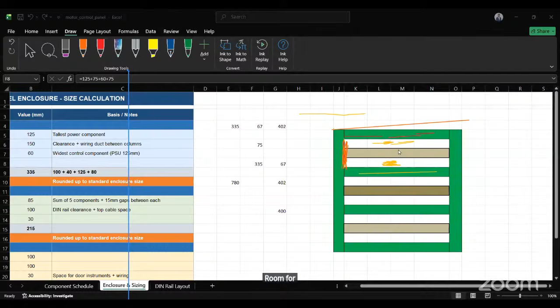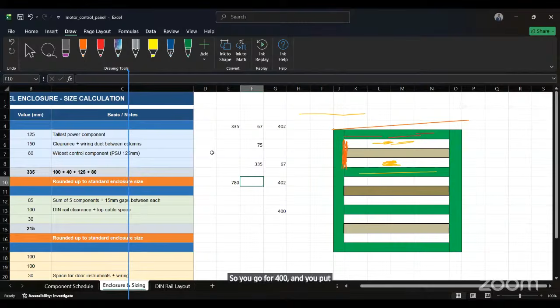0.2 is 20%, so that gave us 67. We now do 335 plus 67, we have 402. The closest to 402 in terms of panel choices is 400. You can't go for 415 or 430, so you go for 400, then you put the 400 back here.